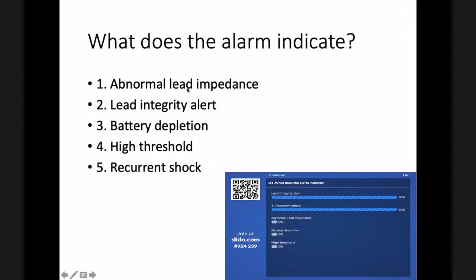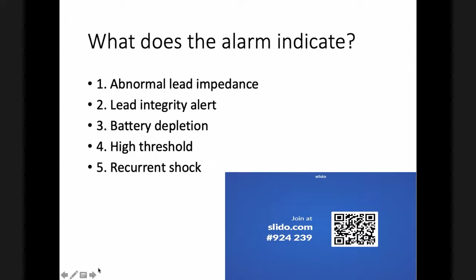So if there are non-physiological intervals being detected, or the lead impedance has changed significantly but it is not out of range, still the lead integrity alert might present with this sound, or if there is a battery depletion, the similar sound can come. High threshold and recurrent shock does not usually give rise to this kind of alarm. In this case, which was implanted just 2 months back, we can essentially rule out a battery depletion. So possibly these two are the most likely culprits, which we will go and interrogate the device and it will tell us. So when we interrogated the device, there are multiple episodes of ventricular fibrillation being documented.